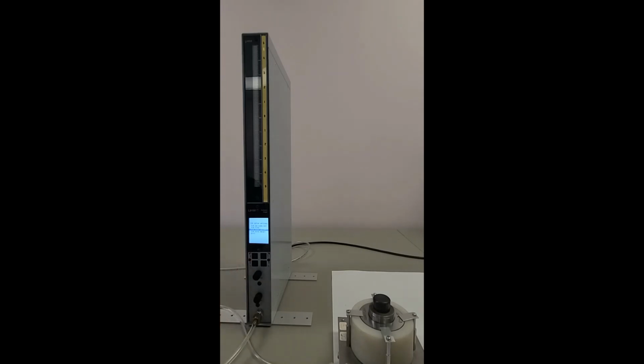In normal TIR operation, as the part is turned in the fixture, dimensional samples are periodically taken and the display is updated to show the current maximum values during the sweep. This process only samples a minimum number of measurements, however, and you could miss flaws if the part is turned rapidly in the fixtures, for example in an automated process.